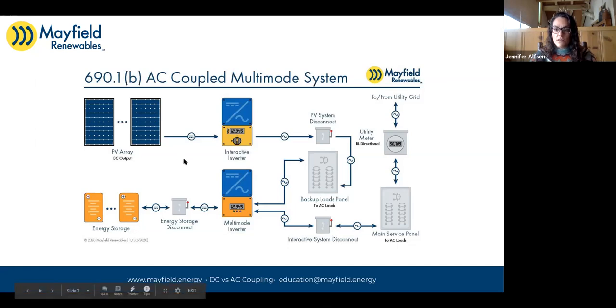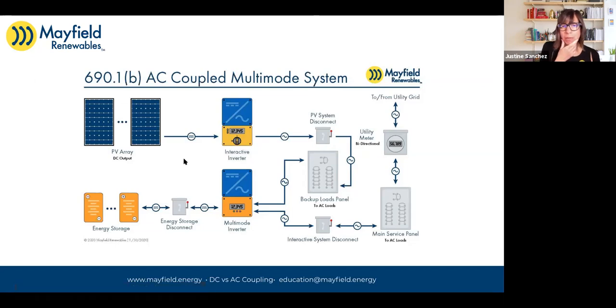But yeah, she brings up a good point—you don't have to co-locate the inverters, and that is one of the advantages, actually. Another advantage we should add to this list is that we could have your interactive inverter remotely located on a different part of the structure. If you get into big systems, it is common for those inverters to not be co-located very close together, although then, like she said, you need switch gear and other componentry to make it all happen. But yes, that is absolutely a way to do it.